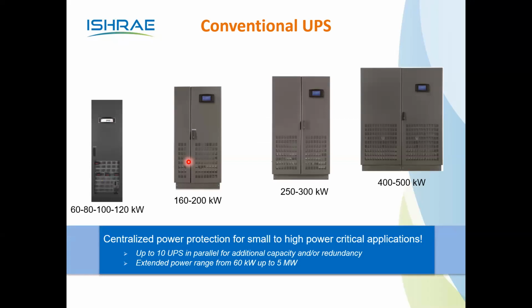So coming to the conventional UPS systems, the picture it is showing is 60 kVA and above. Your eyebrow may be rising here, because you can see that the rating is in kilowatt, not in kVA. That is the main thing here. Most of the technology is designed for kVA. In the sense, the output power factor of the UPS systems may be 0.8 or 0.9 or sometimes 1. So we have to give some attention to this point.